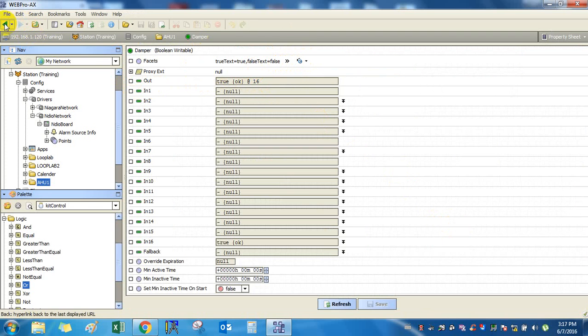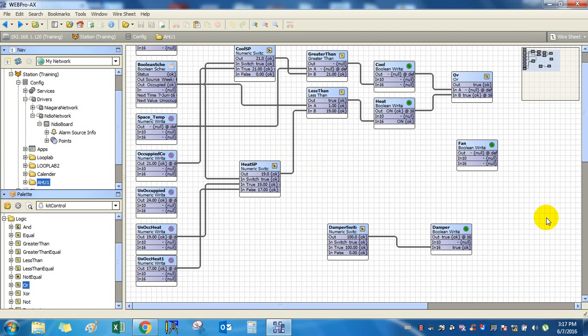So right now I haven't given anything to space temperature input, that's why both heating and cooling are off, but the fan is running, because whenever there is occupancy your fan should run. So directly from this your fan is running and your damper is at 100% position, but heating and cooling both are off. So if you want to check it, right click, go to actions and override. Let's override the temperature to 18.